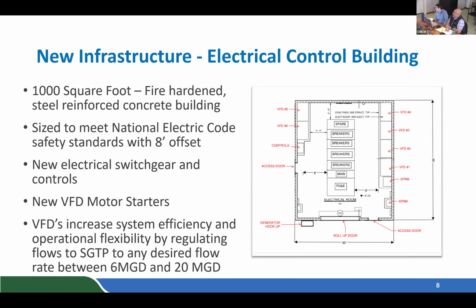Again, VFDs were specified for this project because they increase the system efficiency and operational flexibility, and we can now regulate flow at San Geronimo Treatment Plant to any flow rate between 6 million gallons per day and 20 million gallons per day. The way that's going to work is the operator at the treatment plant will type in essentially their desired flow rate. So if they wanted 16.5 million gallons per day, a computer program is going to tell the pumps to turn on, and they'll actually find their optimal efficiency points. They'll go to full speed, but then they'll lower it down to maybe 70% of their normal speed, and maybe another pump kicks on, but it's actually more efficient to run the pumps at a slower speed rather than full speed. And it'll figure that all out in the background.